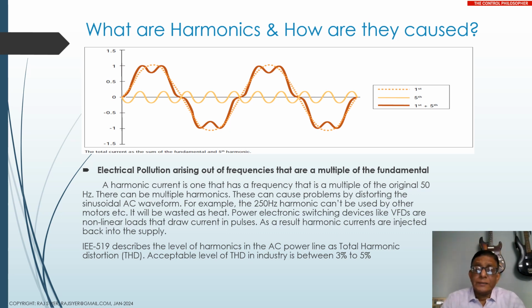What really happens is the inductance of the motor, the capacitance of the cables and things like that respond to the square wave impulses and create additional transients. These transients are not immediately apparent, but you can see them on an oscilloscope. Now, the damage caused by them is also not apparent, but they will reduce the life of other electronic equipment which is sharing the same power supply.